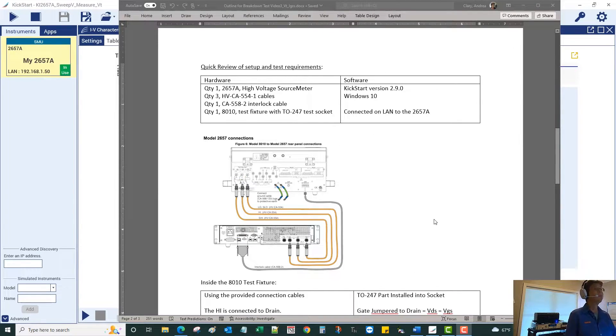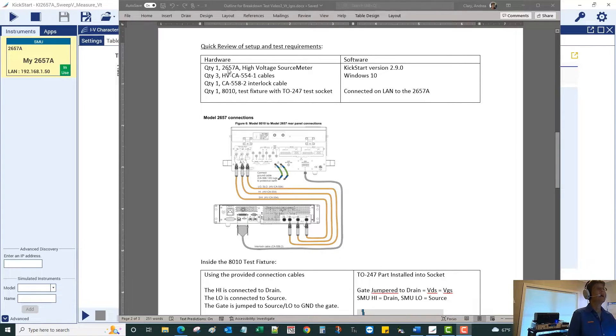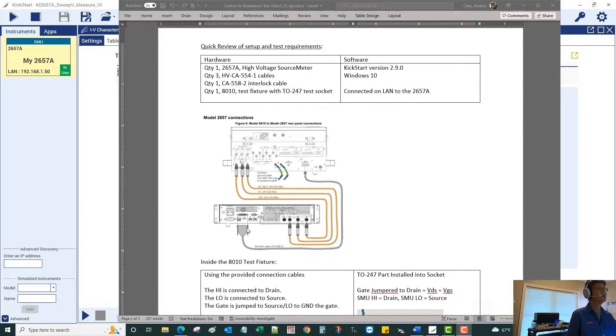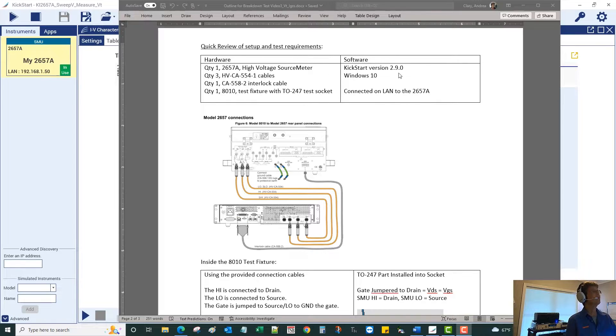Quick review of the test setup: I have a 2657A source meter, with three high-voltage triax cables connecting the source meter to my 8010 test fixture. Since this is a high-voltage source meter there is a safety interlock, and we use a cable to interface the source meter to the door switch on the chamber. To operate it all, we're going to use KickStart version 2.9 software installed on Windows 10, connected over LAN to the 2657A.